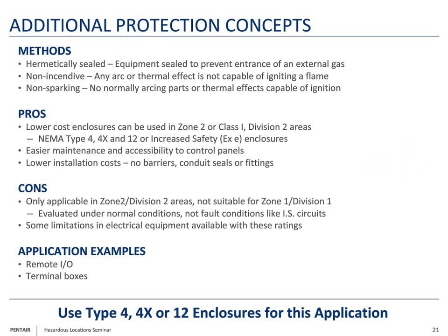There are other alternative protection concepts, so hermetically sealed. This basically means the equipment is sealed and doesn't allow hazardous gases into the system. Typically it's an all welded construction. Non-incendive means any arc or thermal effect is not capable of igniting a flame, and non-sparking means the system or the electrical component isn't going to normally arc under normal conditions. The pros: it allows a lower cost enclosure solution, type 4, 4X, or 12, or you can use increased safety enclosures. They're easier to maintain, and they have lower installation costs.